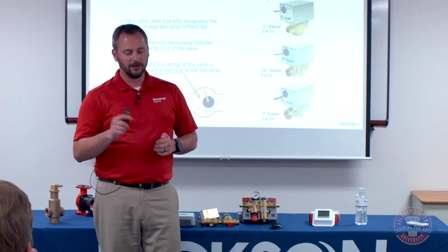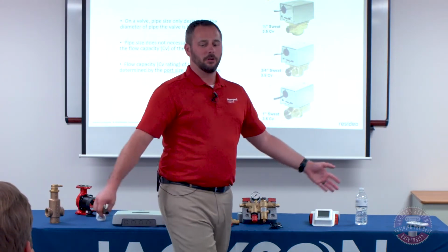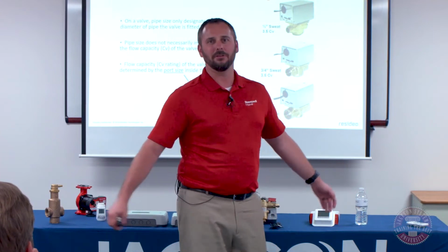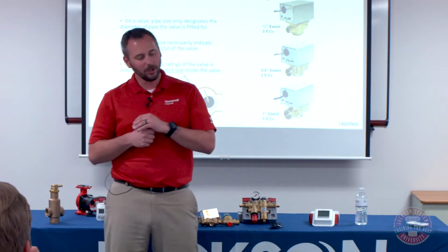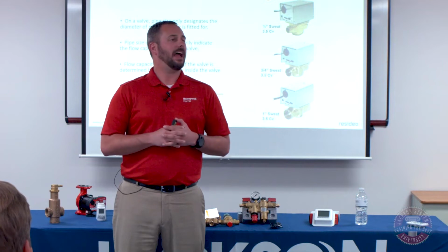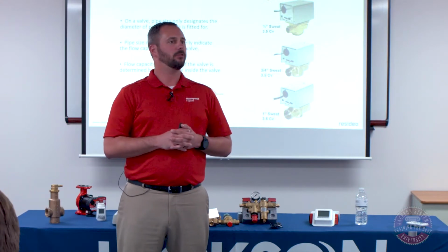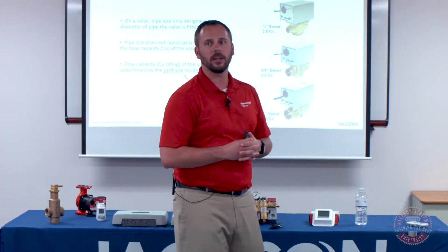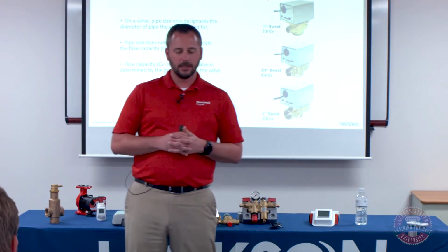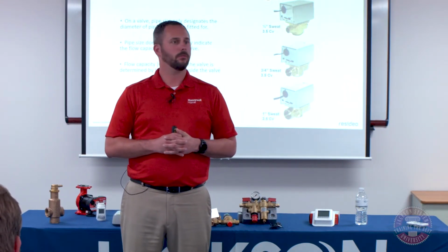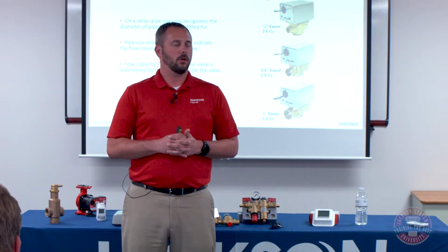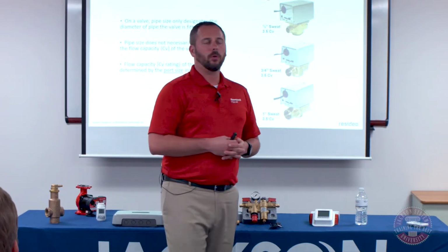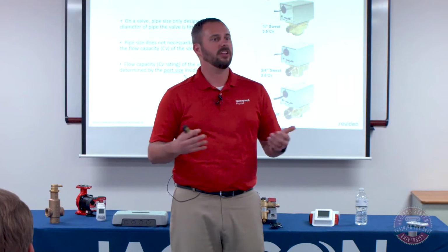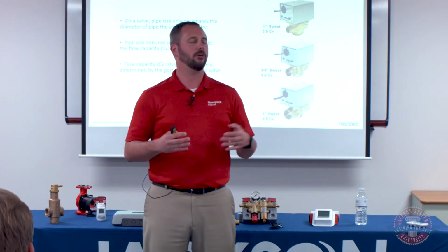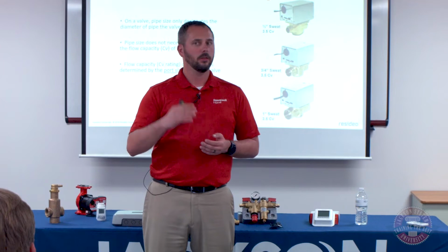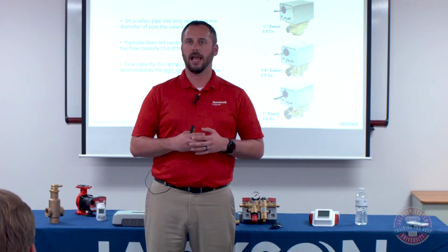Let's see, CV rating. We're going to get into a little bit more math. I apologize in advance. So we make sizes 1/2 inch through 1 inch. I get people on residential systems that go to 1 1/4 inch, and the reason they go to 1 1/4 inch is because they need more flow. Every valve, whether it be a zone valve or whatever, is going to have a CV rating on it. That CV is essentially telling you what the pressure loss through the valve is. The smaller the number, the more resistance you're going to have.